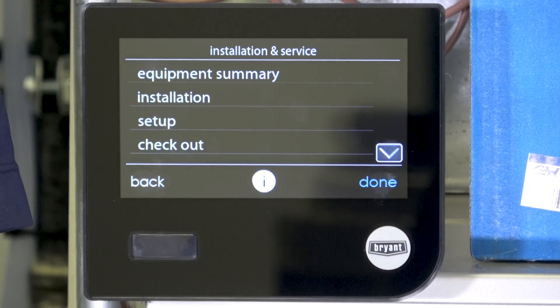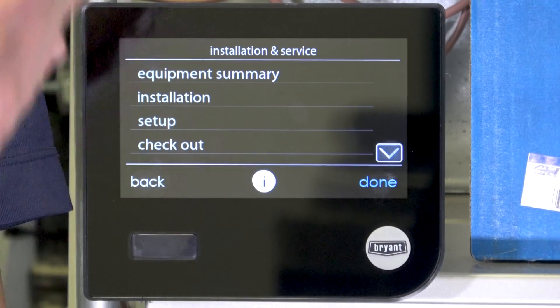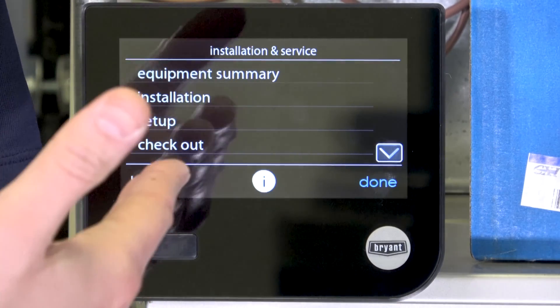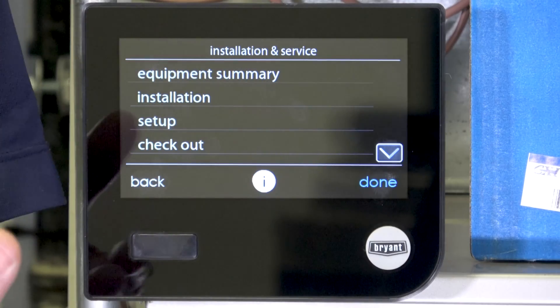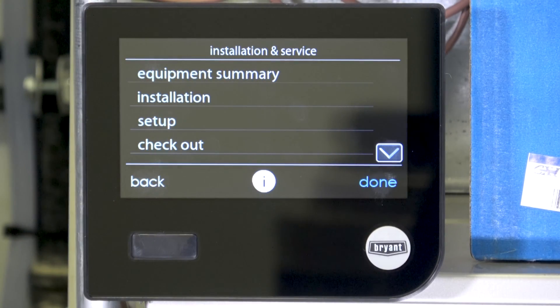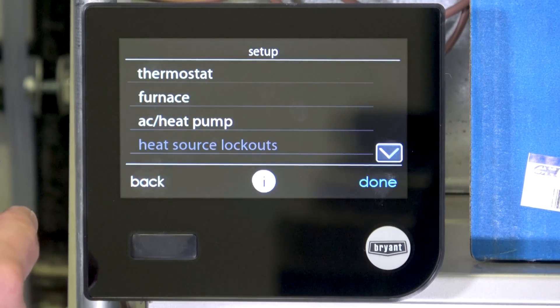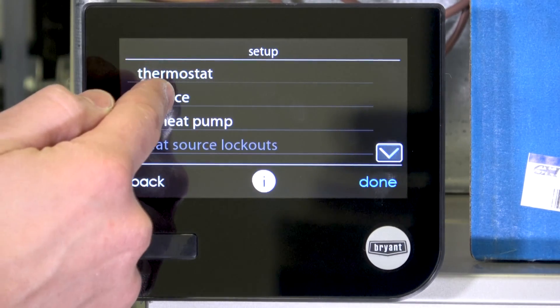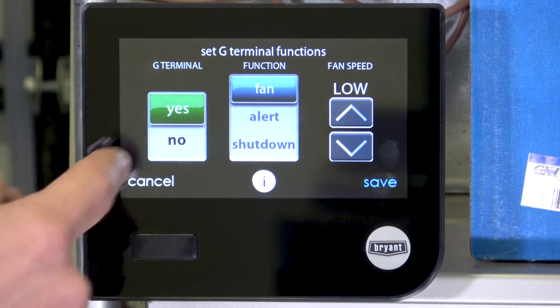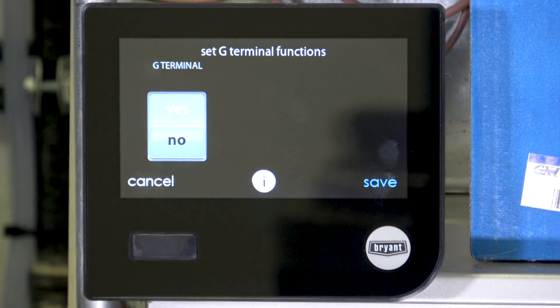Now that we have the detector wired up to the furnace input, we need to tell the wall control, the Bryant Evolution, Carrier Infinity or ICP Ion wall control what to do with that message. All right, so once I'm in the service screens, I'm going to select setup. I'm going to select furnace because I'm wired to the furnace circuit board and I'm going to scroll down to where it says G terminal. It normally would look like this. It would have nothing on it.